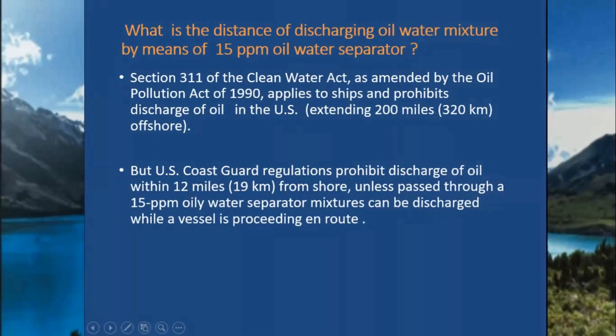The discharging of oil mixture is governed by the 15 parts per million (ppm) oil water separator standard. Based on Section 311 of the Clean Water Act, as amended by the Oil Pollution Act of 1990, this applies to ships and prohibits discharge of oil in US waters extending 200 miles or 320 kilometers from shore.